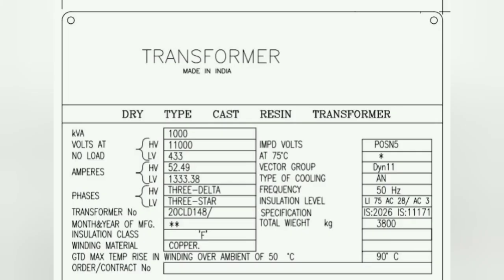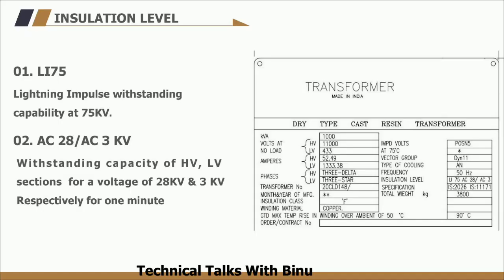The next parameter is the insulation level, written as Li75, AC28 bar AC3. Li75 means the HV winding lightning impulse withstand voltage is 75 kV. Impulse tests are normally performed on transformers to check insulation levels. AC28 bar AC3 means the continuous withstanding capacity of the transformer for a high voltage of 28 kV on the HT side and 3 kV on the LT side respectively, for a continuous duration of 60 seconds.